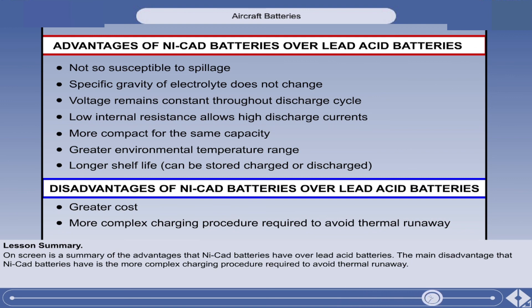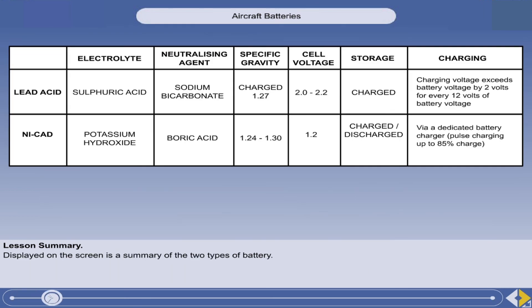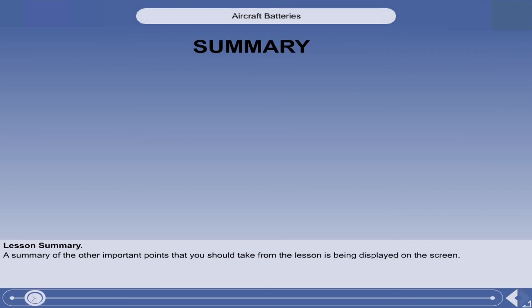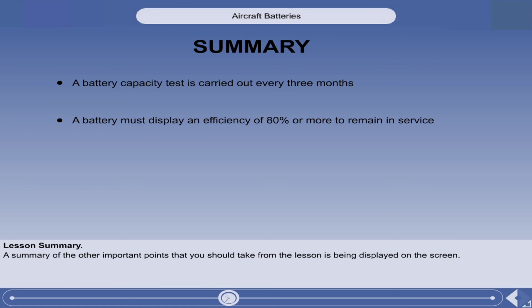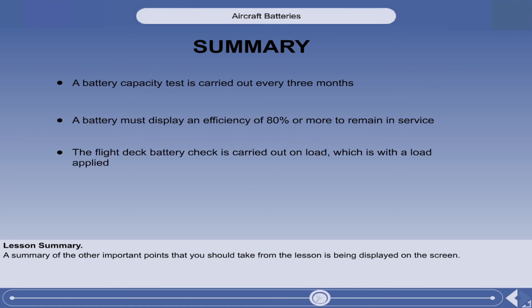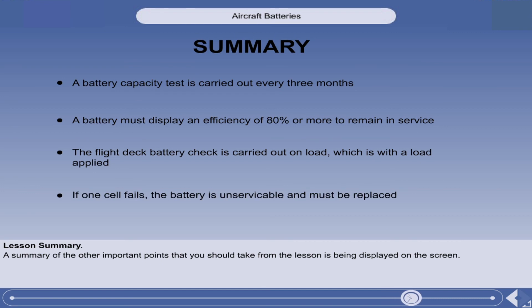Spend a moment studying the comparison table, then move on when you are ready. Displayed on the screen is a summary of the two types of battery. Here are the other important points you should take from the lesson: a battery capacity test is carried out every three months; a battery must display an efficiency of 80% or more to remain in service; the flight deck battery check is carried out on load, which is with the load applied; and if one cell fails, the battery is unserviceable and must be replaced.